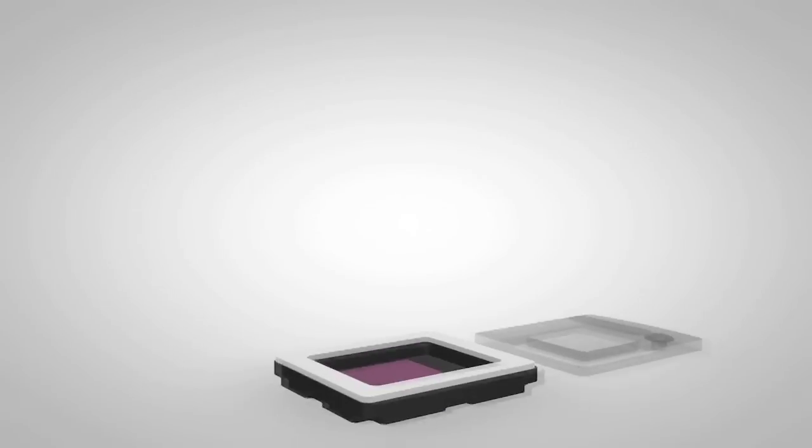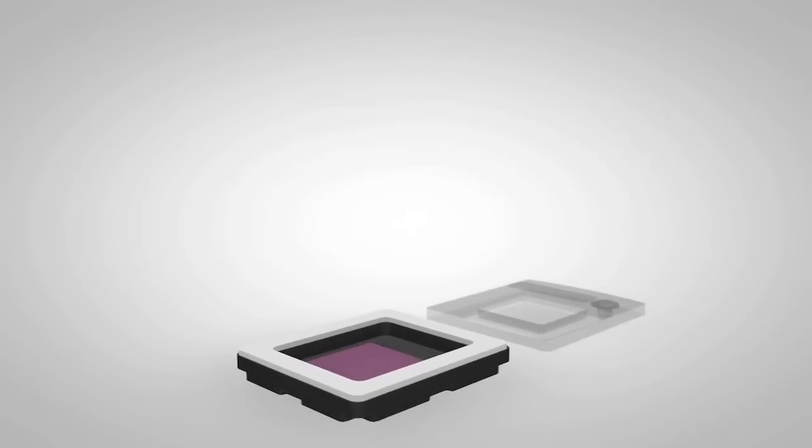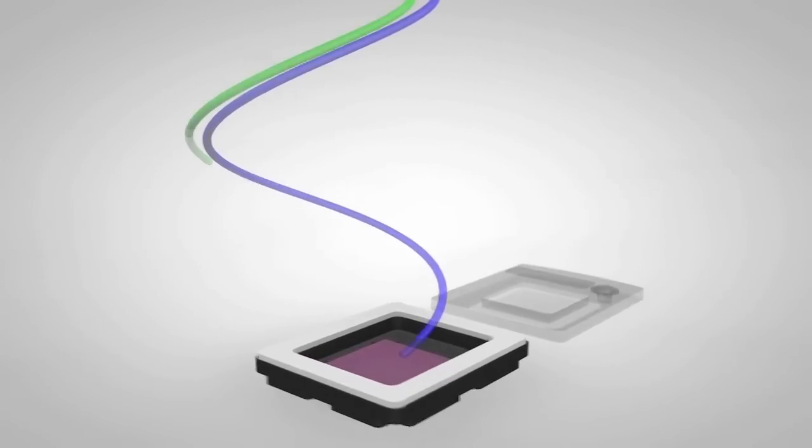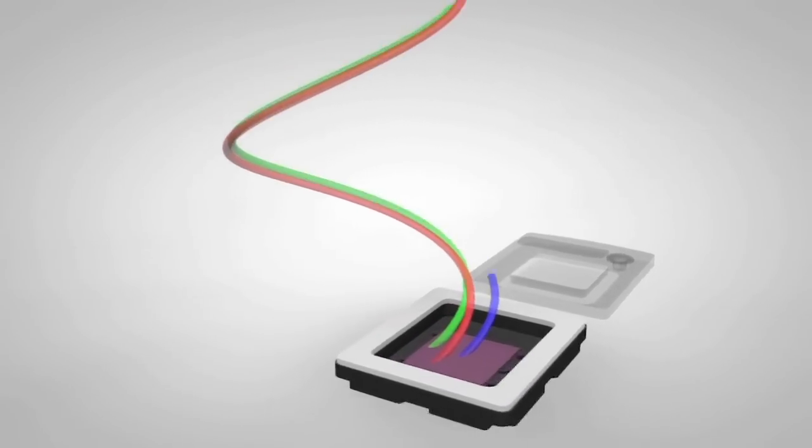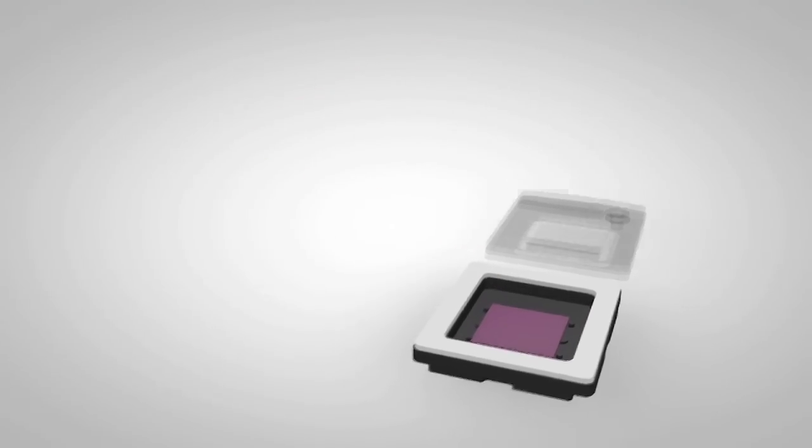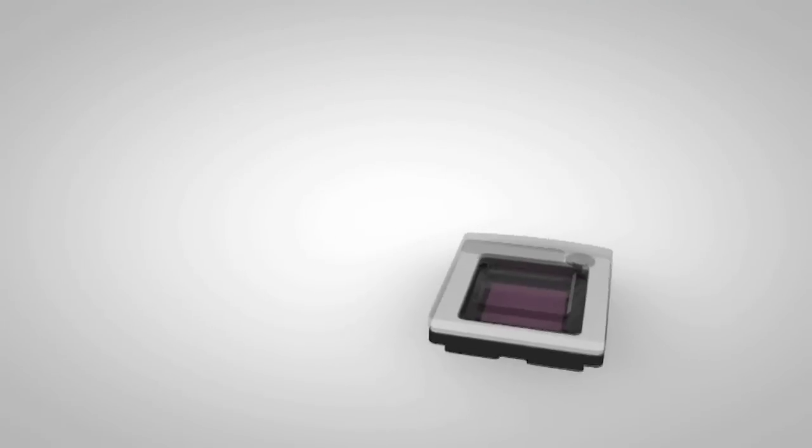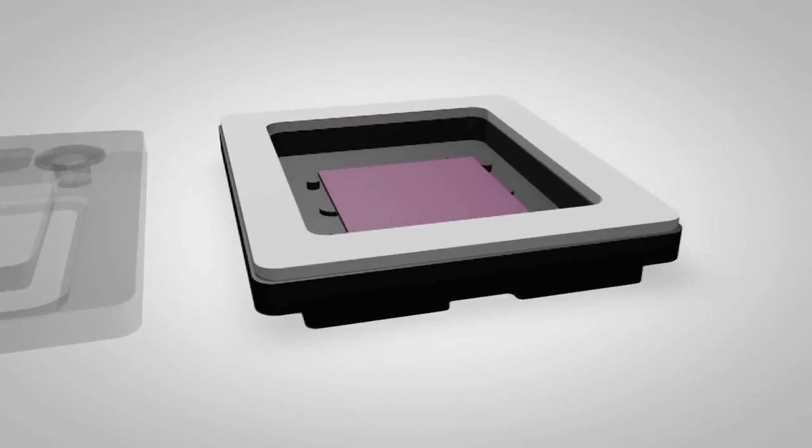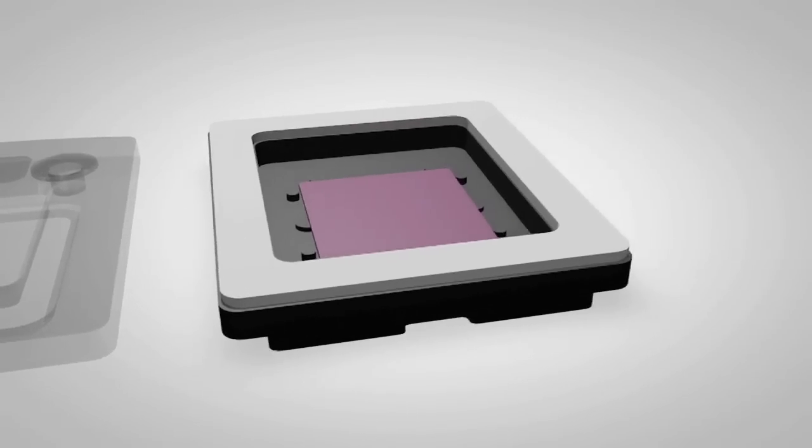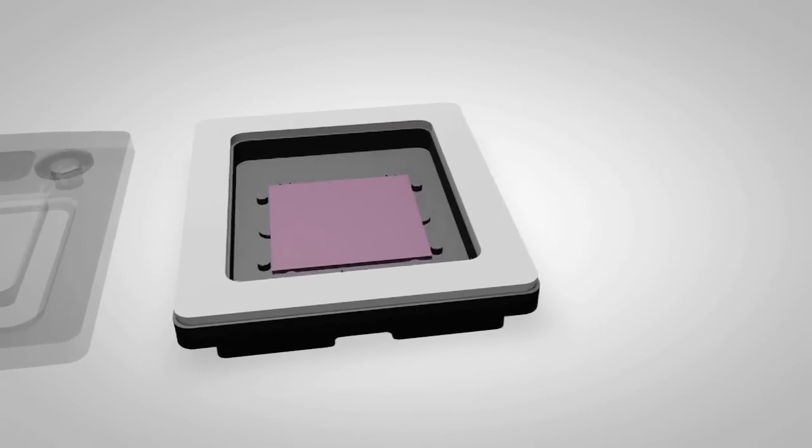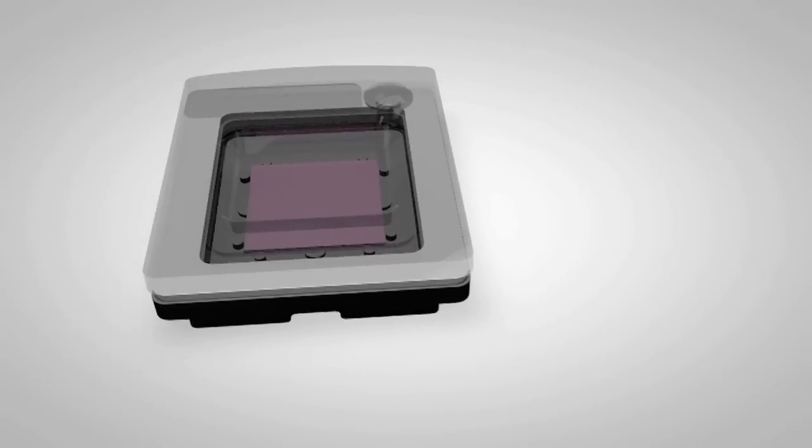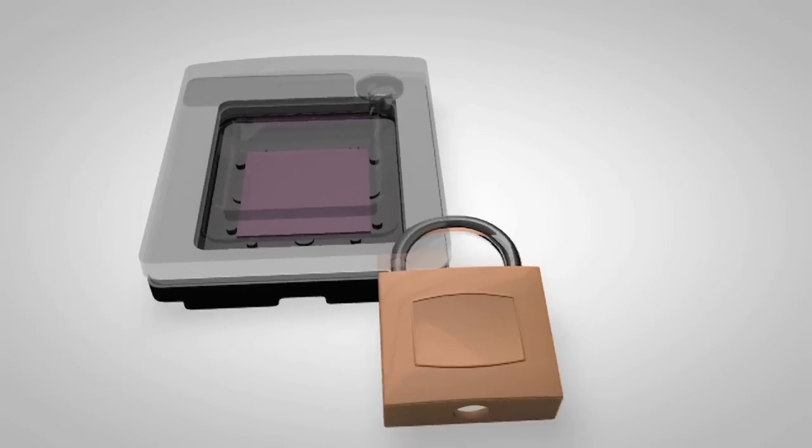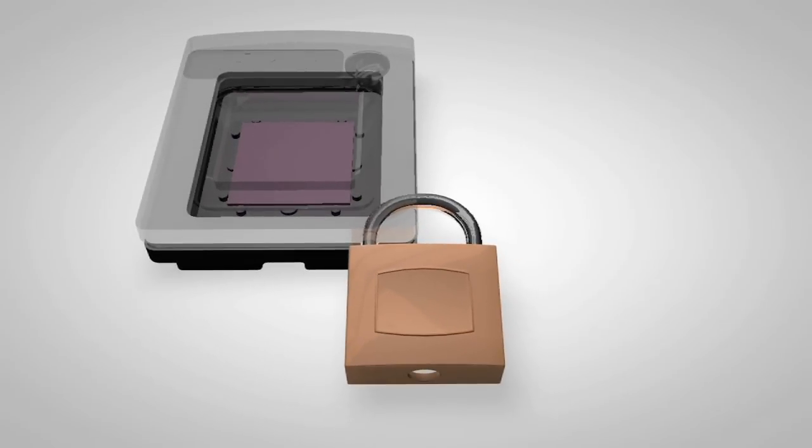The use of a chip enables a streamlined workflow with minimal pipetting steps. Once the sample, assay and master mix have been combined, the reaction mix is loaded onto the chip and the chip is sealed with a lid. Once closed, the chip will not be opened again, eliminating any possibility for the release of high copy DNA amplicons into the surrounding lab environment and minimizing exposure to environmental contaminants.